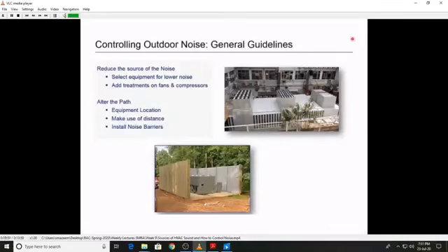How do you go about controlling the outdoor noise from your units? Well, in general, you have the same two choices as you have anywhere in noise control. You can reduce the source of the noise by selecting equipment that inherently makes lower noise, or by adding treatments on the fans and compressors of the equipment itself. Or you can alter the path of the sound. You can change the equipment's location. You can make use of distance. Remember, sound decays with distance.